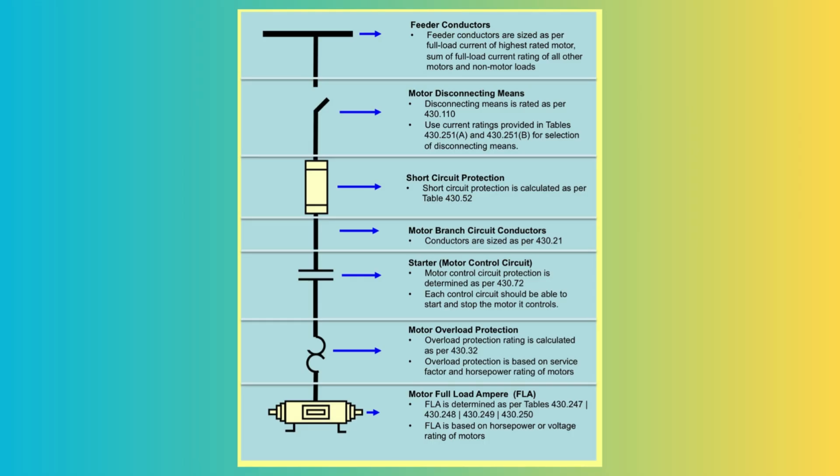Feeder conductors. Feeder conductors are sized based on the full load current of the highest rated motor combined with the sum of the full load current ratings of all other motors and non-motor loads.